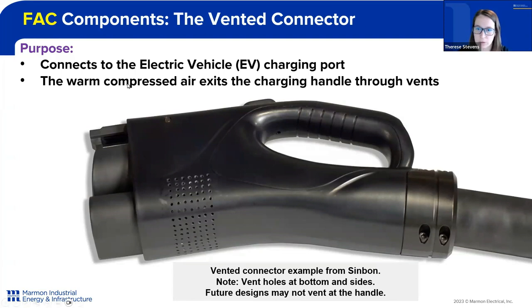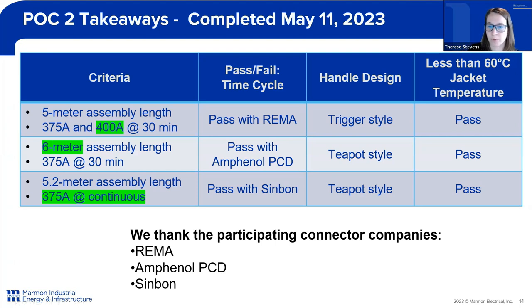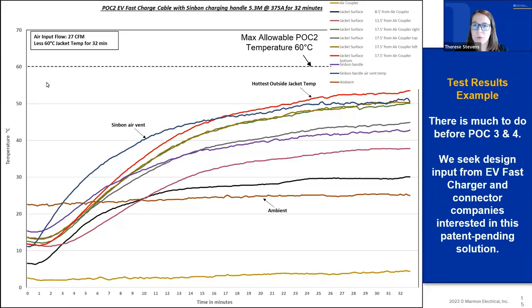I want to talk about our proof-of-concept 2 takeaways. We did this testing on May 11, 2023, at our East Granby, Connecticut facility. We were able to test three different connector manufacturers with our arm and cable. We successfully achieved testing with all three connector manufacturers at 375 amps and 400 amps for several different cable lengths. By successful, we mean we were able to keep the cable at a safe operating temperature as dictated by the customer. We really appreciate all the support from REMA, Amphenol PCD, and Sinbon — we wouldn't have been able to get these results without their support.